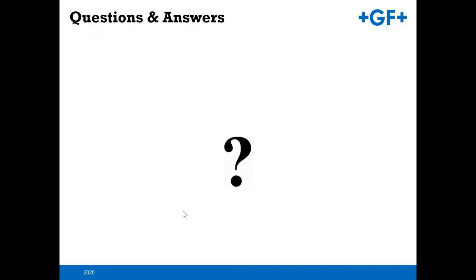Okay. Yeah, maybe in that option might be a thermal device. I know that Gilson, being the applications guys that you are, maybe that would be something you could take off on. Okay. I believe that Ryan Dean and the gentleman that asked that question are going to talk about that offline. I'd just like to point out that an 800 PSI line with an insertion is really asking for trouble. I agree. The amount of pressure behind there and the ability to launch that thing is a major league safety precaution, and we wouldn't want to do anything insertion style that way. I agree.